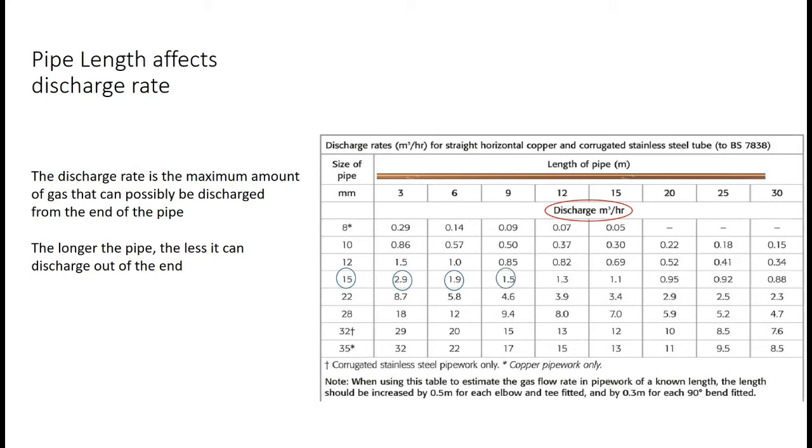If you make it longer to 9 metres, it goes down to 1.5, then 12 metres 1.3 and 15 metres 1.1. So the longer the pipe is, the less gas can be passed through it.